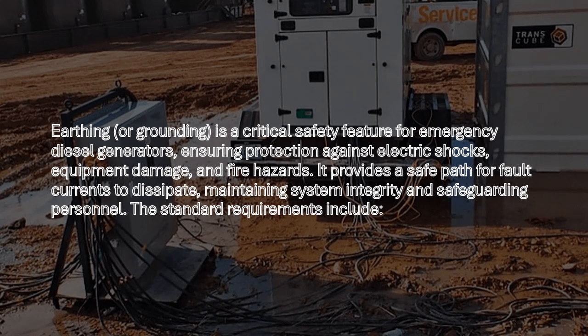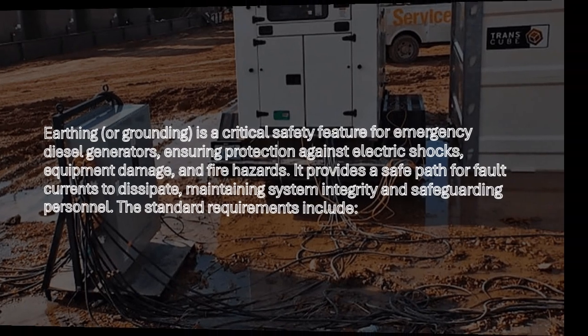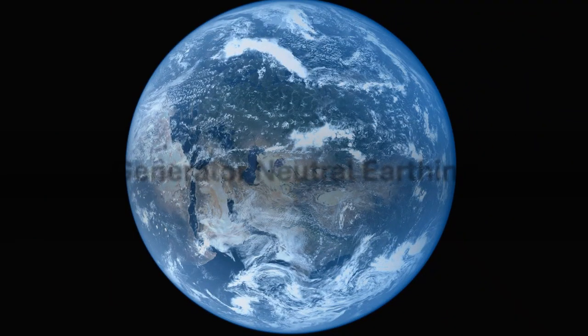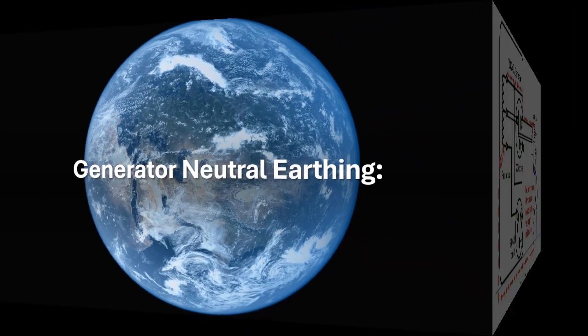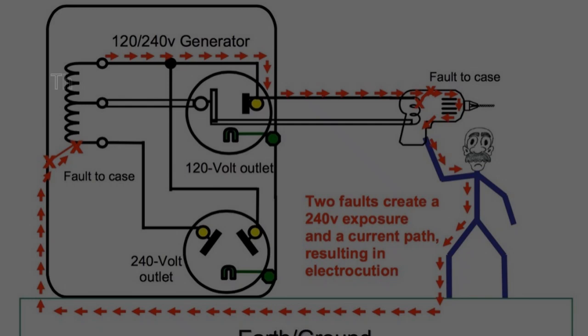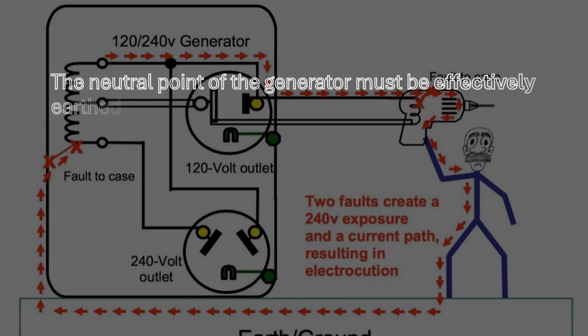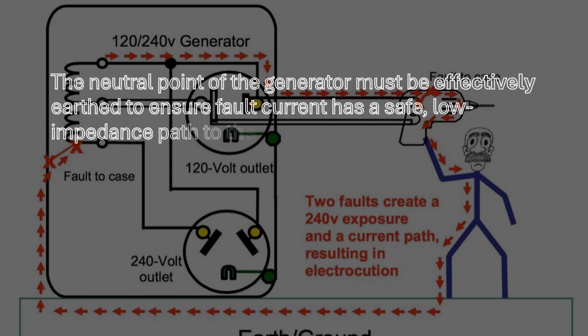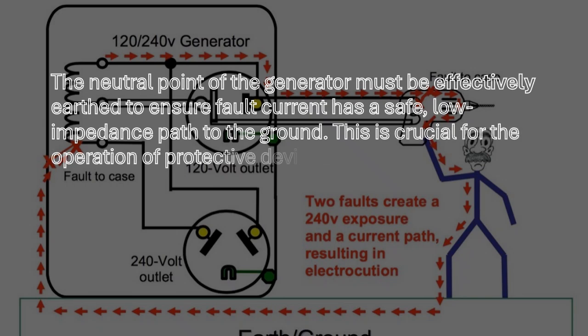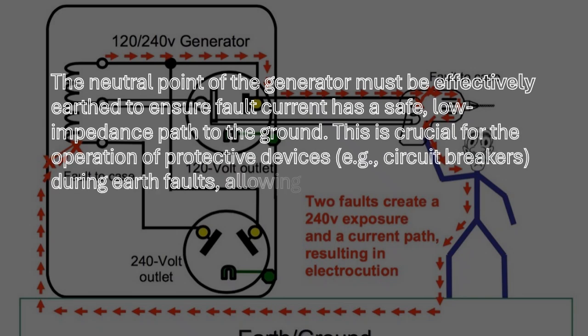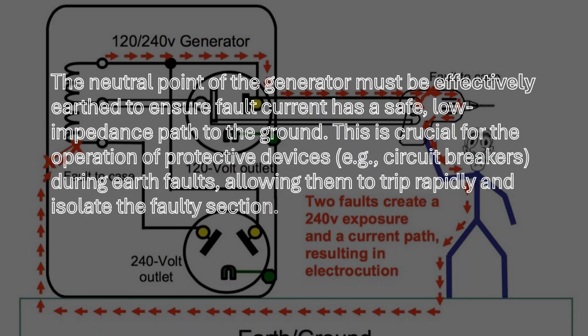The standard requirements include generator neutral earthing. The neutral point of the generator must be effectively earthed to ensure fault current has a safe, low-impedance path to the ground. This is crucial for the operation of protective devices, e.g., circuit breakers, during earth faults, allowing them to trip rapidly and isolate the faulty section.